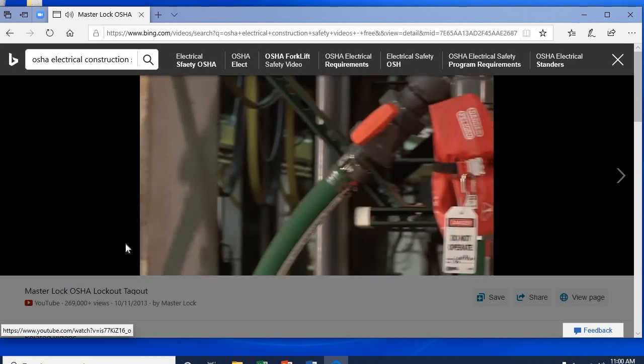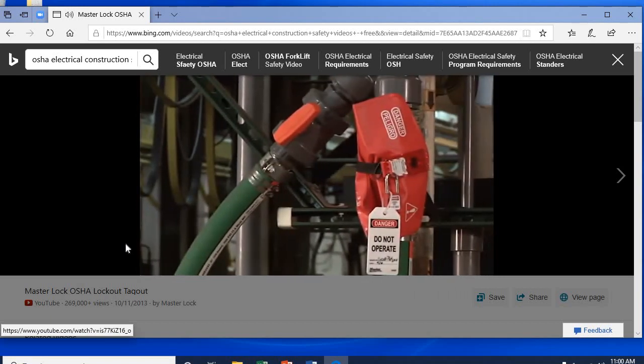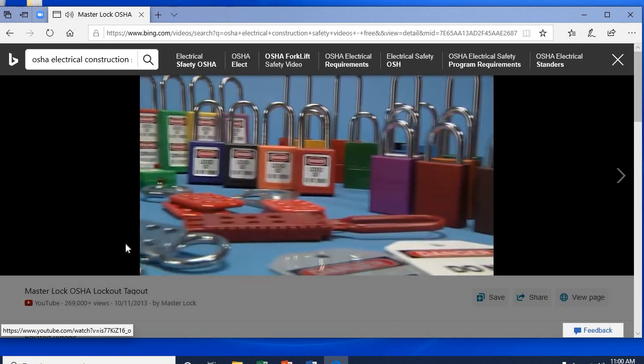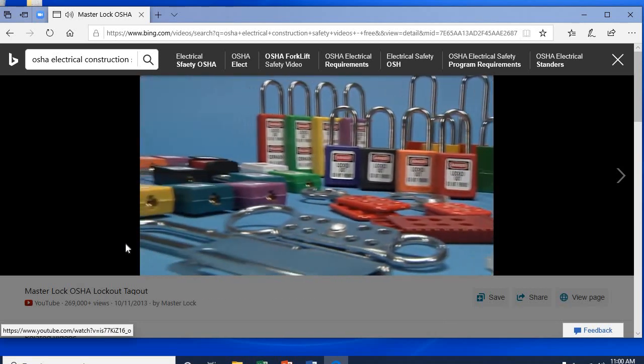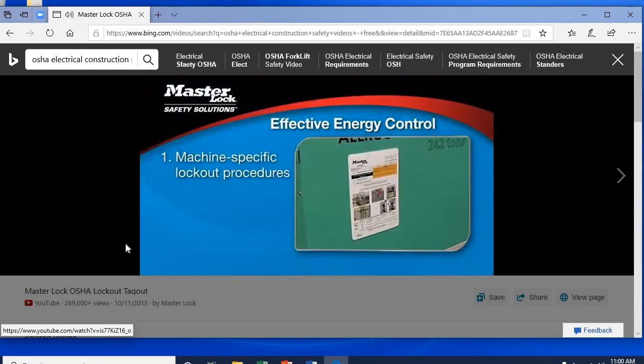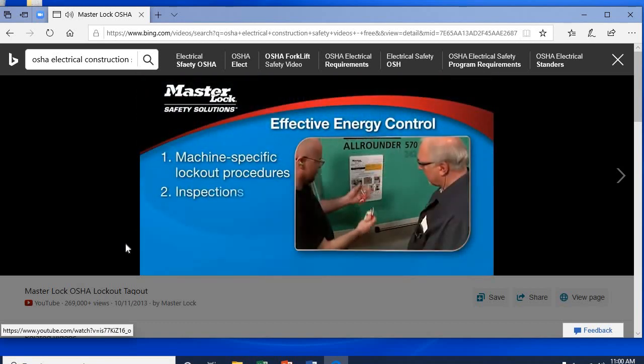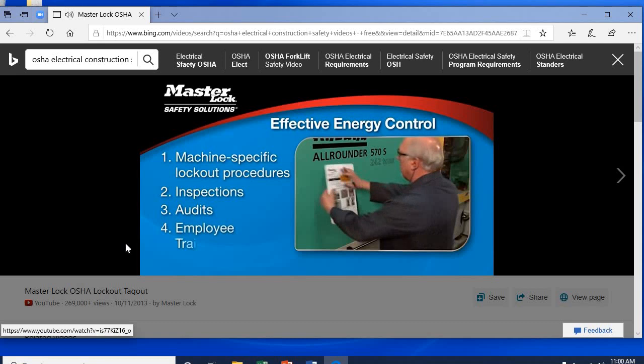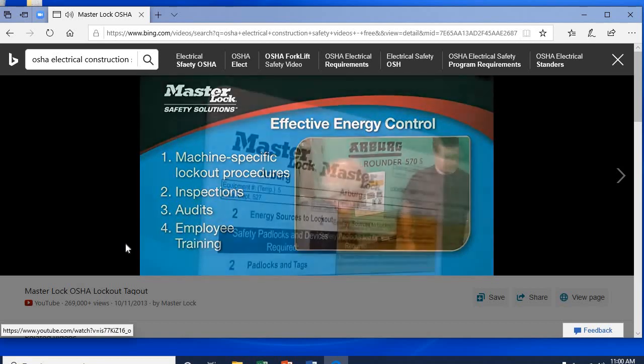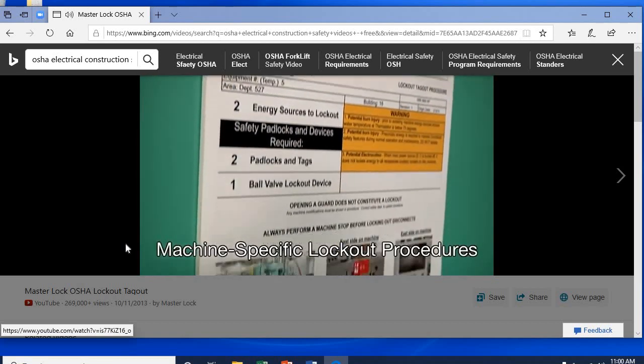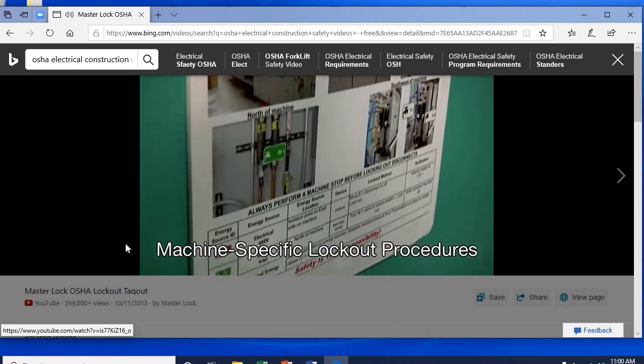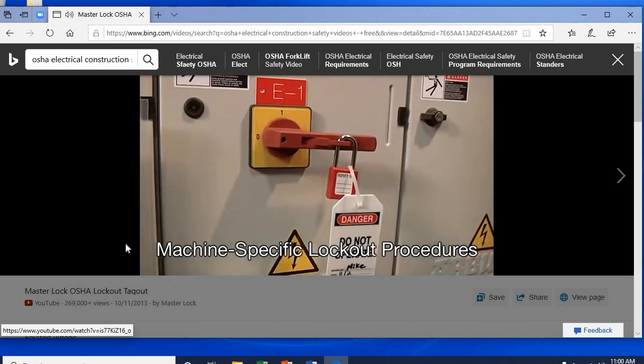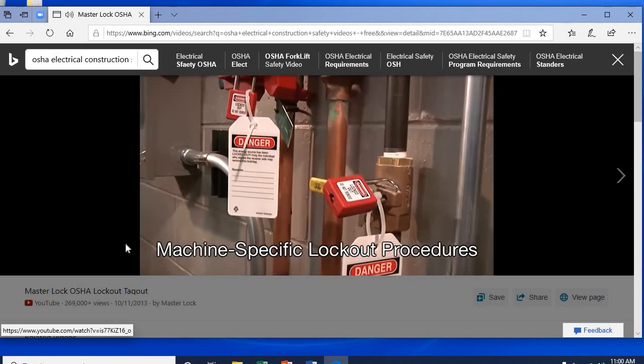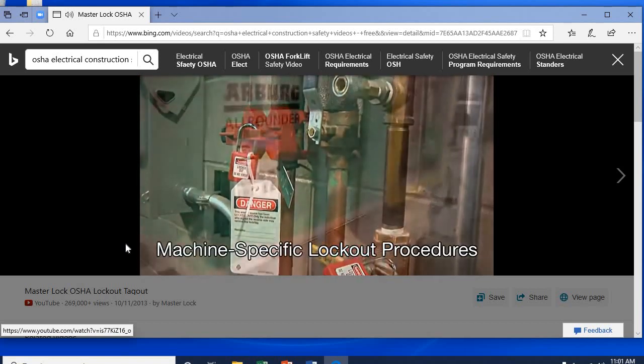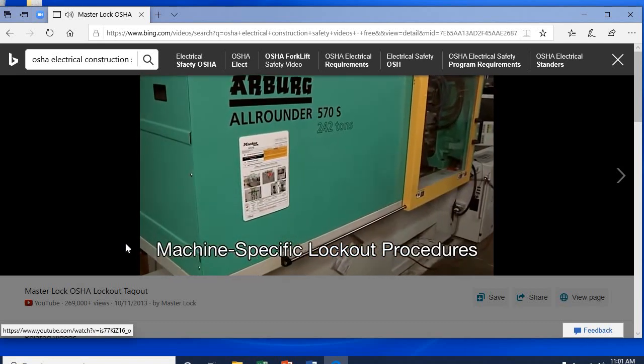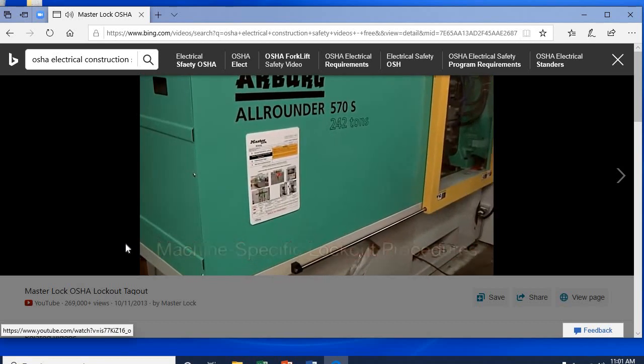There are four key components to an effective energy control program. Beyond having sufficient safety padlocks and lockout devices on hand, there needs to be machine-specific lockout procedures, inspections, audits, and employee training. Machine-specific lockout procedures outline the specific steps and requirements that an authorized employee needs to complete to safely lock out a piece of equipment. This includes posting the procedure at the equipment location for easy reference.